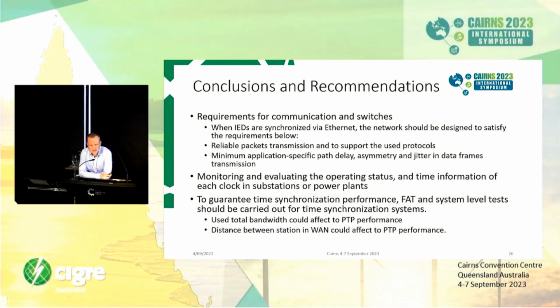Does the actual distance matter or is it more the number of hops? The number of hops is more important. Sure, the speed of light is something, but it's always the same, so in that sense it does not matter that much. It's more really the number of hops, because every hop involves equipment, and every piece of equipment, even the good ones, will have some inaccuracy. And the number of hops matters because there are inaccuracy requirements calculated per box - so every box adds that amount. And also bandwidth will affect the performance.